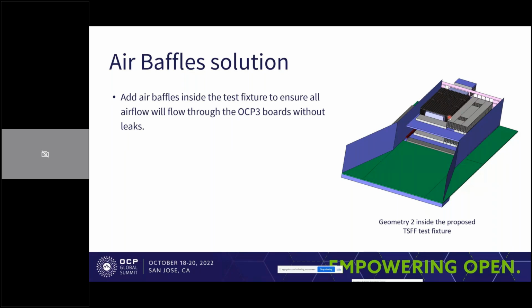We need to make some difference here. So if we push the total airflow, for example, we need to calculate the CFM according to this internal cross-section area, because this is our effective cross-section area when all the airflow goes to our cards.